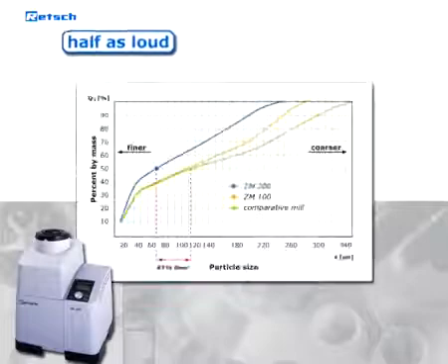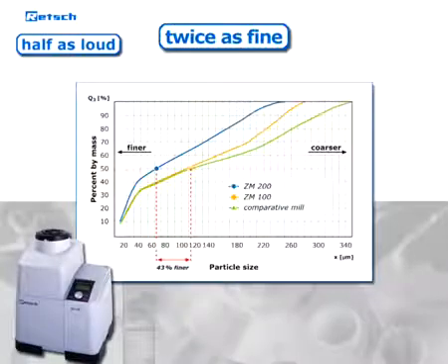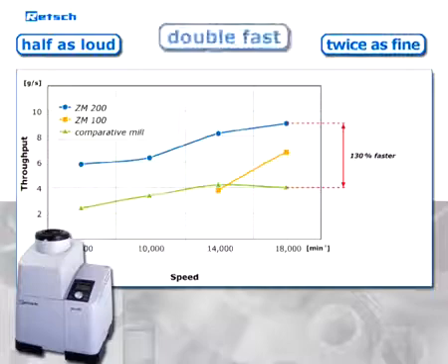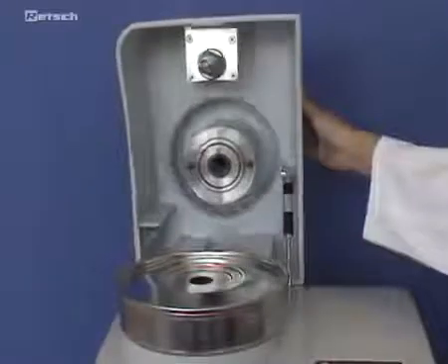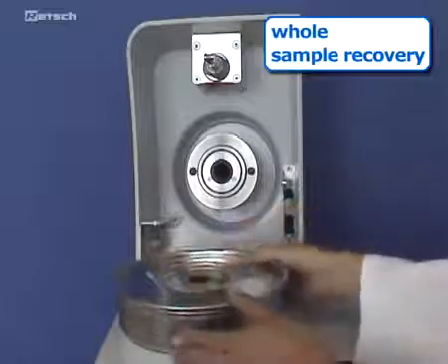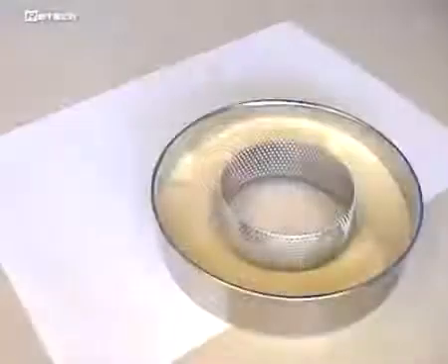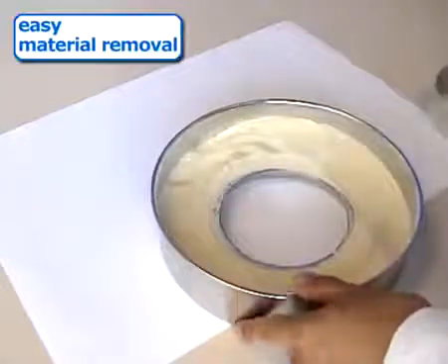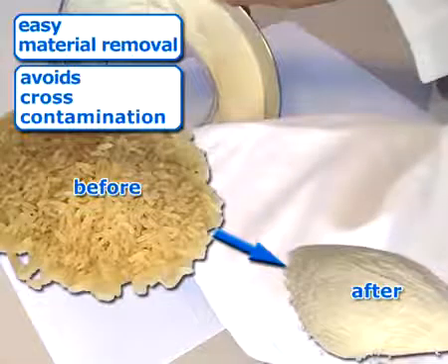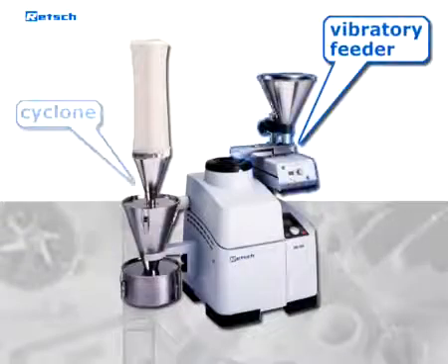Due to its enormous speed constancy, the ZM200 achieves grinding results that are about twice as fine as compared to traditional centrifugal mills. Moreover, higher throughput thanks to the optimally matched frequency converter and three-phase motor reduces grinding time by a factor of two. After the grinding process is completed, the cassette can be taken out together with the sieve, so that — different to other centrifugal mills — the whole sample can be recovered. All grinding components can easily be removed for cleaning. The innovative and patented cassette principle ensures easy material removal and avoids cross contamination.